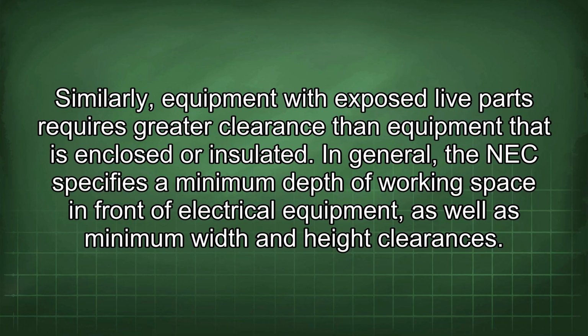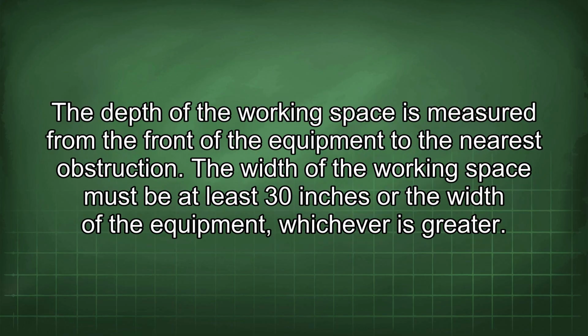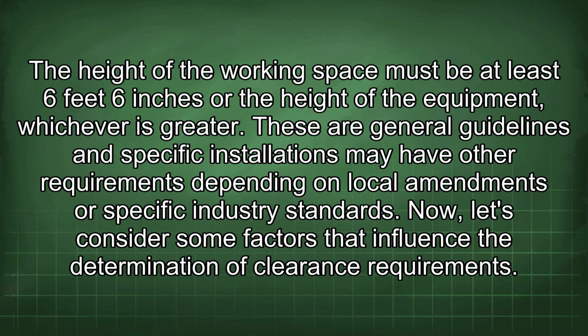In general, the NEC specifies a minimum depth of working space in front of electrical equipment, as well as minimum width and height clearances. The depth of the working space is measured from the front of the equipment to the nearest obstruction. The width of the working space must be at least 30 inches or the width of the equipment, whichever is greater. The height of the working space must be at least 6 feet 6 inches or the height of the equipment, whichever is greater. These are general guidelines, and specific installations may have other requirements depending on local amendments or specific industry standards.